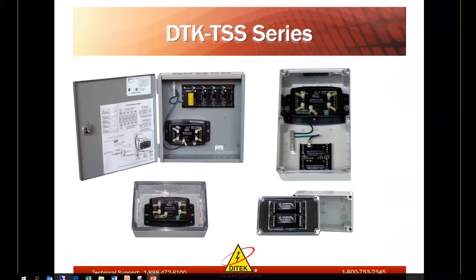Here is our TSS series, which we call Total Surge Solution. These are perfect in many low-volt applications, but great for fire protection. The first one in the upper left is a TSS1. That utilizes the 120SRD and a NEMA enclosure with a 5MB multi-base, meaning it's 5 bases conjoined together for a single point ground that protects up to 10 pair.